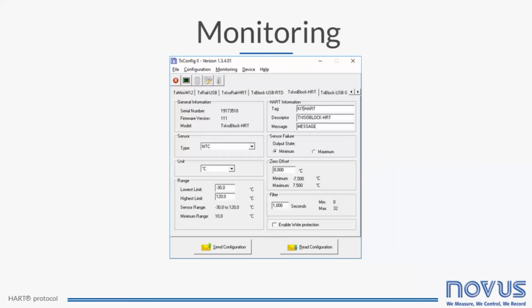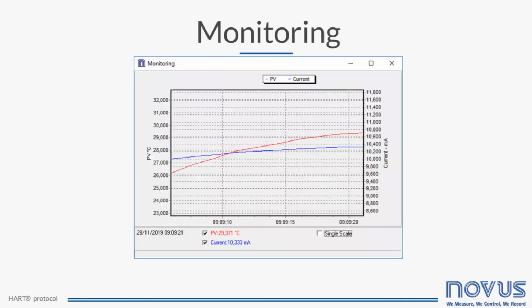NOVUS offers proprietary free software, the TxConfig II, for configuration and diagnosis of NOVUS HART devices. Its user-friendly interface has the necessary configuration options, which are easy to set. Just select the modem's COM port and the software will automatically recognize the device. When reading the device, the technician will already have access to the configuration, as well as being able to monitor the parameters in real time at both temperature and 4 to 20 milliamps output, facilitating configuration changes and preventive maintenance.